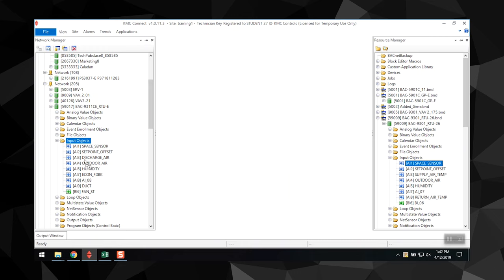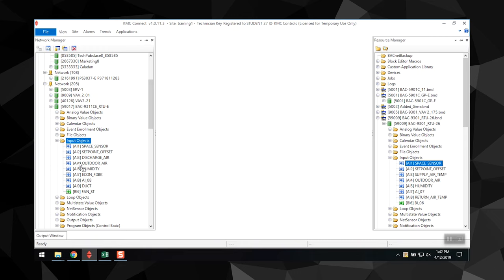You can only drag input objects onto input objects. You can drag a device from a backup file onto a device of the same model and manufacturer. And if dragging a folder to another folder or device, the resource manager restores objects on an instance matching basis. These are only a few of the stipulations for the restore function. We recommend you check the KMC Connect reference manual to learn more.